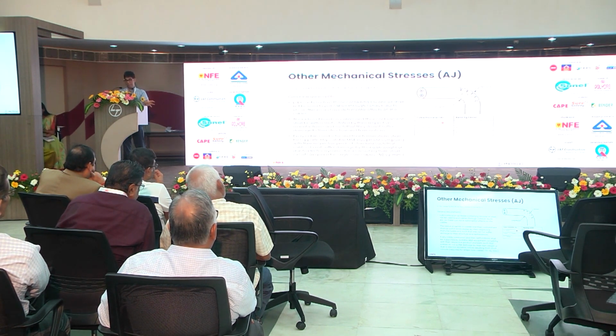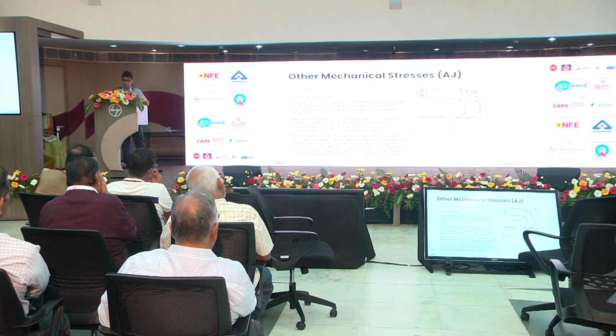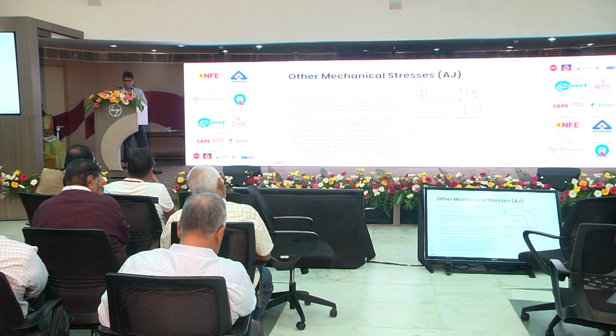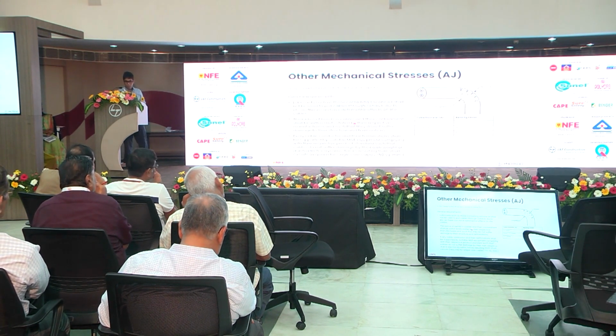And if the information is not presented, you should probably find another manufacturer. For cables less than or equal to 10 millimeter, the bending factor is 3, for 10 to 25, sorry, it is 4, and 25 onwards it is 6. And this applies for containment as well as just clip direct.